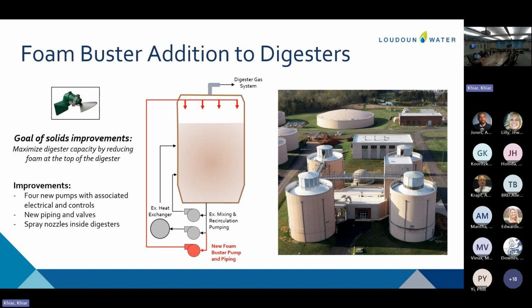These digesters are pretty big, about 65 feet tall, so that pump has to be designed to convey flow from the bottom to the top, and we have a lot of piping there. One thing not shown in these pictures is that the basement of the digesters, where this pumping equipment and piping will be located, is actually really congested with a lot of piping and valves right now. We're confident we'll be able to fit all of this infrastructure in, but it's going to be a bit more complicated. Still, it's a relatively straightforward way for us to knock down the foam currently in the digesters and regain some of that capacity we'll need within the next few years.